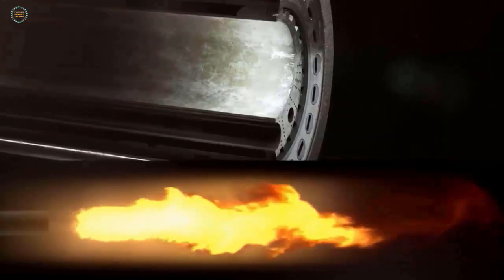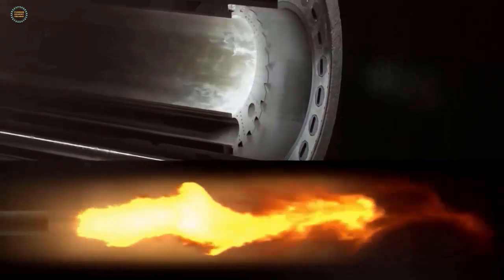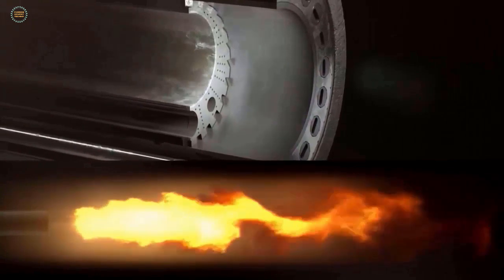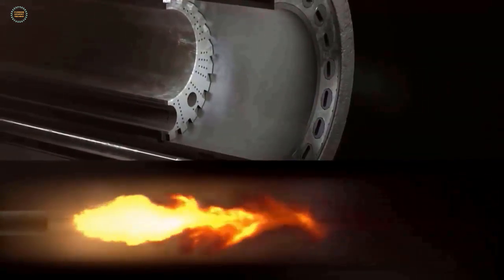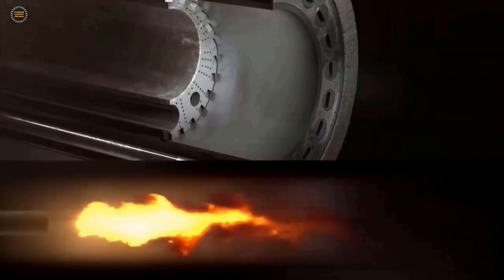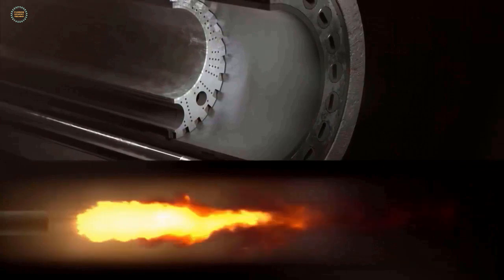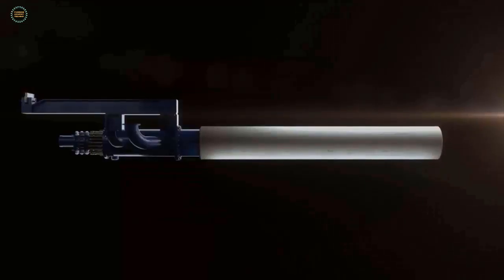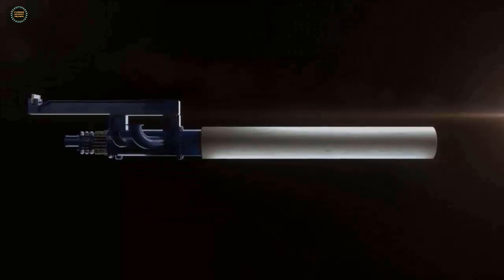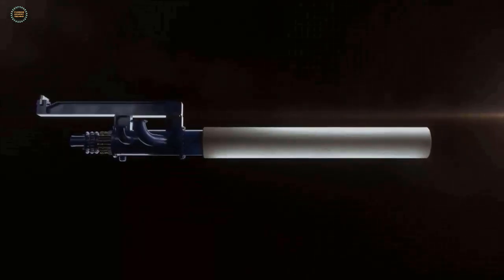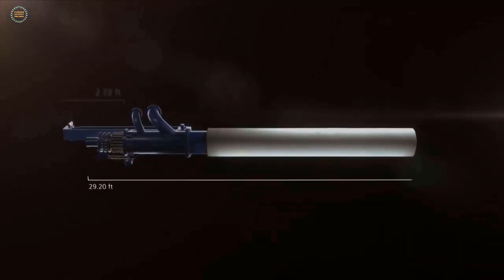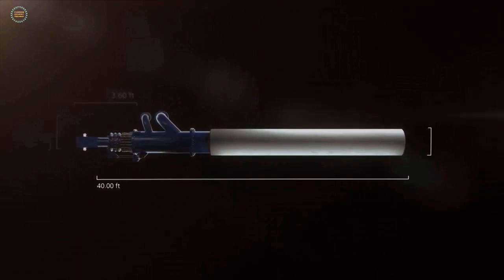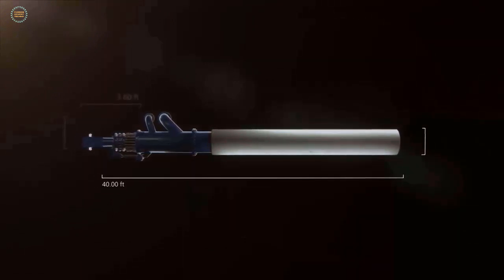The JetFlex Plus burner enables maximum fuel flexibility by superior combustion of lower grade fuels. It features fully rotatable jet air nozzles and a retractable center pipe. The rotatable jet air nozzles enable the flame to be shaped exactly as required by the fuel and process. The nozzles can also be positioned in a fuel lift configuration, which strongly increases fuel retention time and minimizes fuel dropping out of the flame. The center pipe can be retracted, combined with the jet nozzles, allowing a significant drop in fuel velocity, enabling early ignition. The JetFlex burner's simplified design includes a detachable support beam and reduced overall length, making it fast and cost-effective to deliver and install.